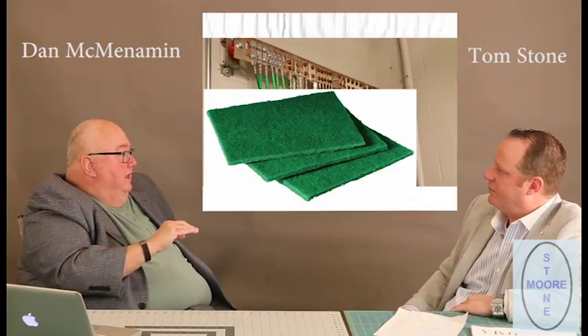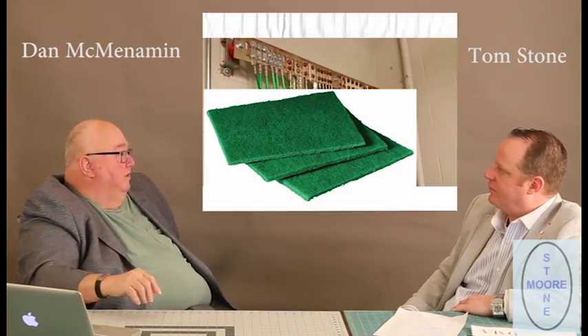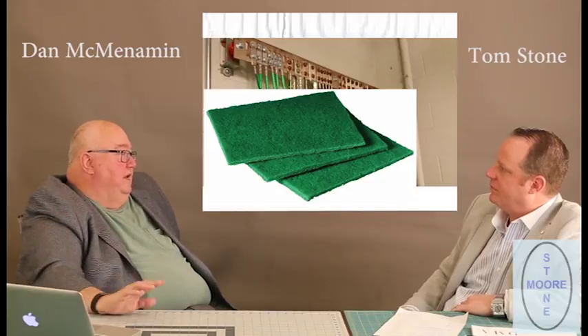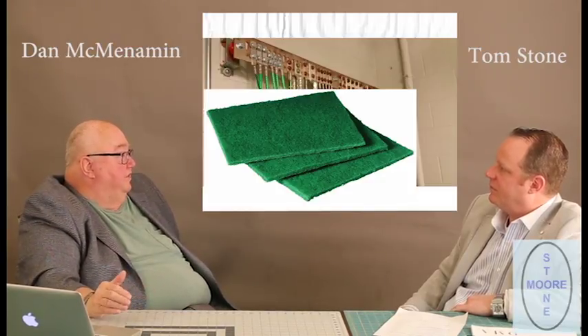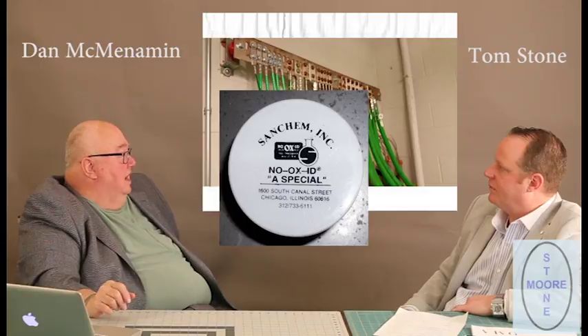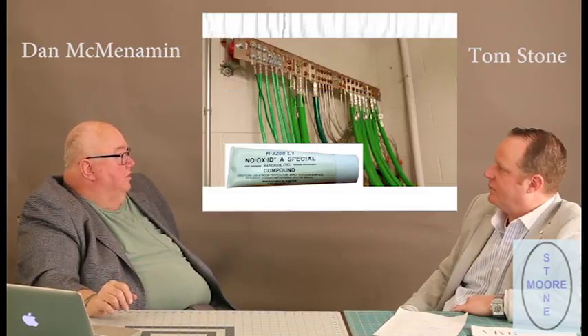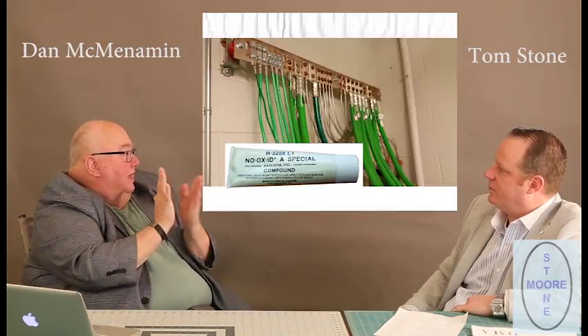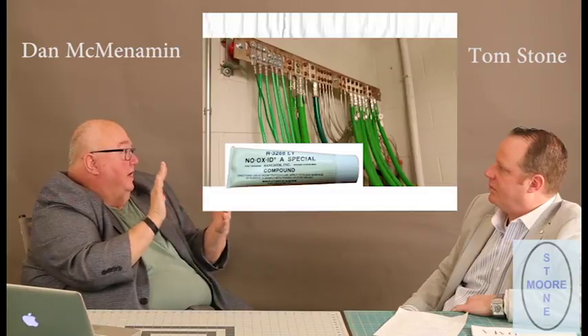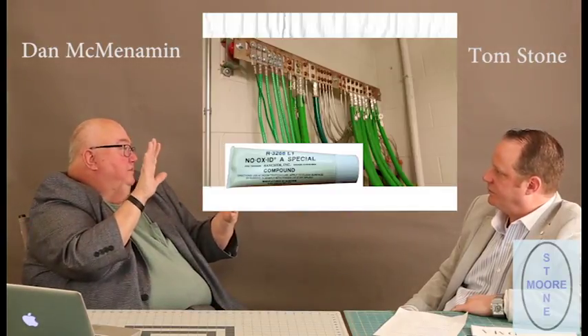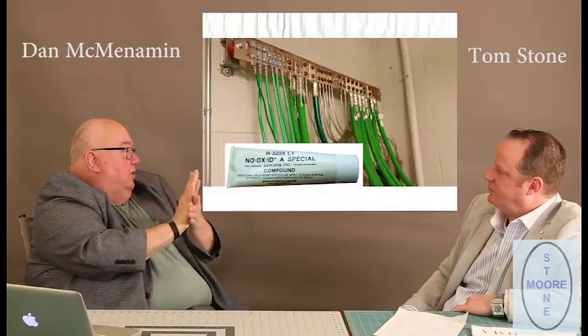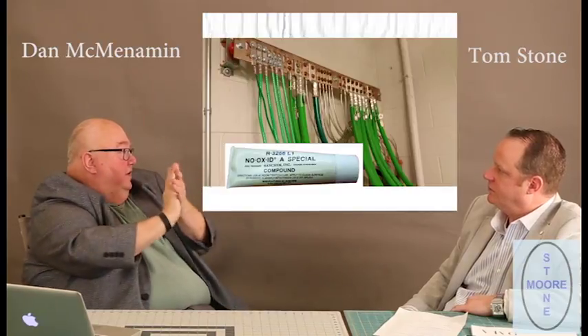And you clean it to a bright finish, and then you put a coating on there of a cosmoline grease. The trade name we use in the telecom industry is No-Ox-Id A Special, made by a company called Sanchem. And there are other compounds out there, but most of the RBOCs prefer the cosmoline grease type. And what that does is keep moisture out of it, so it doesn't set up a corrosion cycle. And so now you have typically a tin-plated lug bolted onto a copper bar from these various things, and then the same thing going down the ground, or CAD welds.